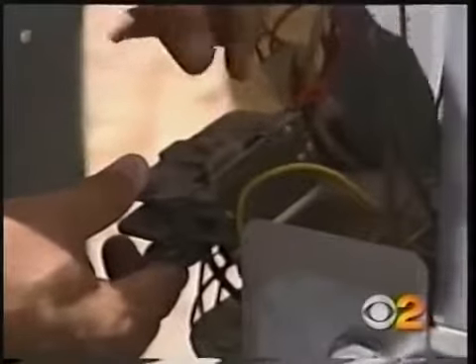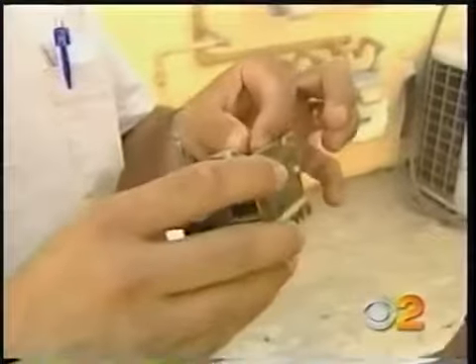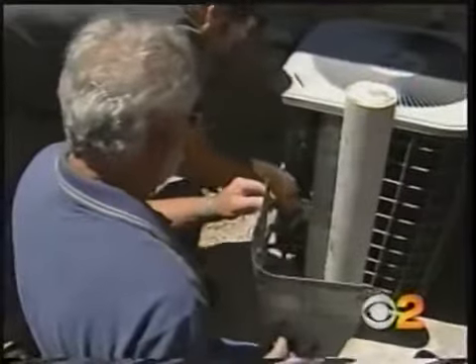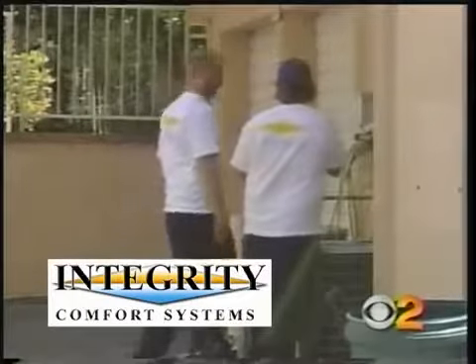He found a wire disconnected. I've never seen one like that, never in 20 years. He says it appeared to have been cut. When contactors typically fail, they burn, the coil will char, but I've never seen a clean cut wire like that. The wire was cut. Cut? I questioned Kevin, but he said he didn't do it. It worked fine, and I didn't cut it.